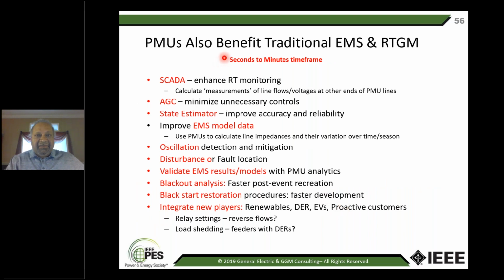PMUs also benefit traditional EMS and real-time grid management, in the seconds to minutes time frame. SCADA: you can enhance real-time monitoring. AGC: you can minimize unnecessary controls, and people are enhancing AGC with PMUs. State estimator: of course the state estimator calculates voltages and angles, and PMUs give you the voltage and angles.